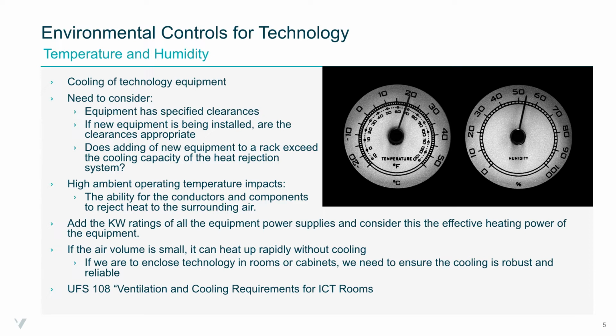So if new equipment is being installed or additional equipment is being installed, there's a potential for a shortfall in the amount of heat rejection that can occur. So this is obviously another good question as a ship manager, as an officer on board, where engineers come on and want to make a change to the installed equipment. How much reserve cooling capacity is there in the system to support the addition of this new equipment? Now, if the vessel's operating at a certain latitude and new equipment comes in and is installed, there may be sufficient headroom in that heat rejection system to ensure that it works fine and continues to operate.